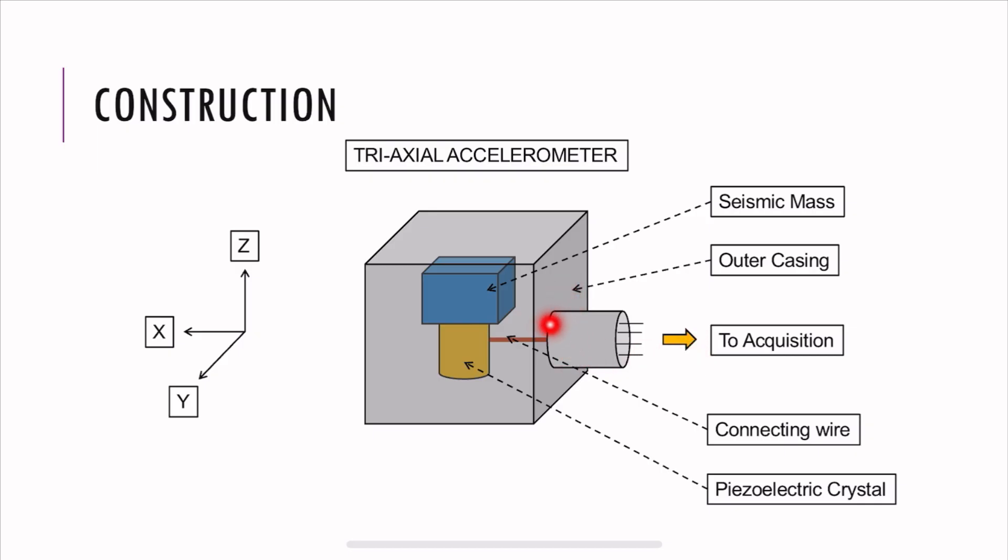These are the directions the accelerometer is measuring. This is like the right-hand thumb rule. The Z represents your thumb finger, the X your index finger, and Y the middle finger. Usually the accelerometers have these directions engraved on their surface. For example, here it'll be like Z, here it'll be like Y, and on the other side that you cannot see will be X. So it means that the accelerometer is measuring those directions if you mount them according to this right-hand thumb rule.